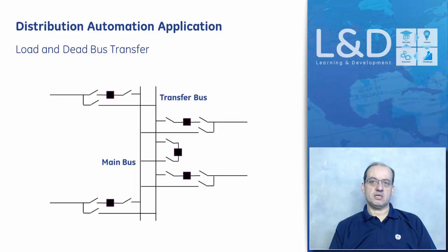The application detects a transformer that reaches a predetermined overload set point, which would be pre-configured for that transformer, then transfers the loads to a station that has unused capacity. The application also automatically attempts to restore power to feeders that lose their primary supply in the station.